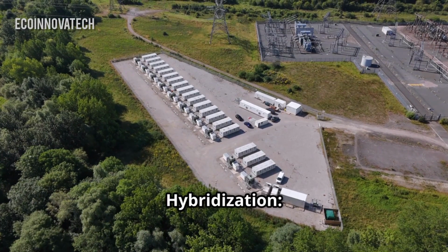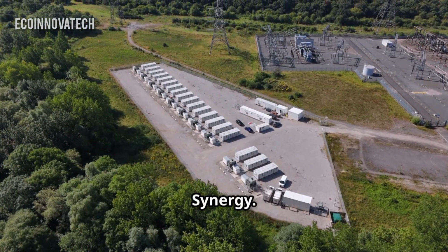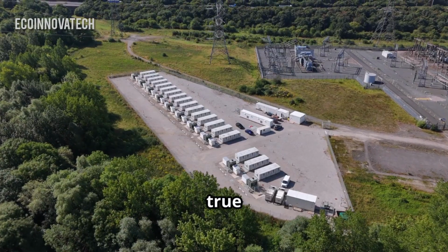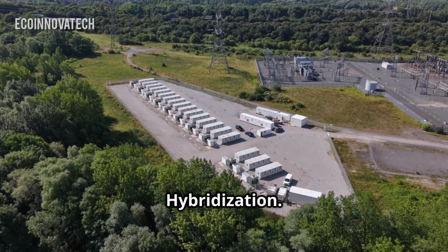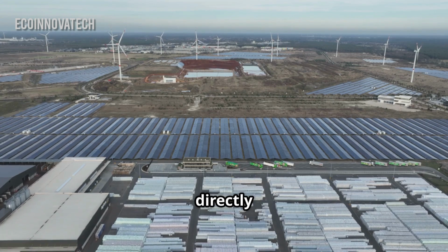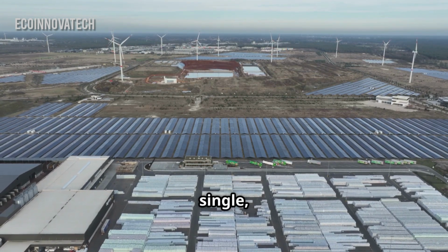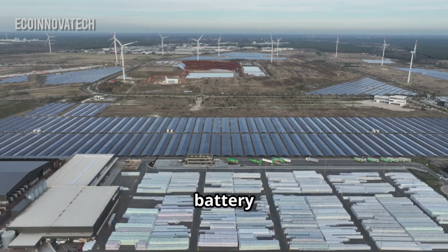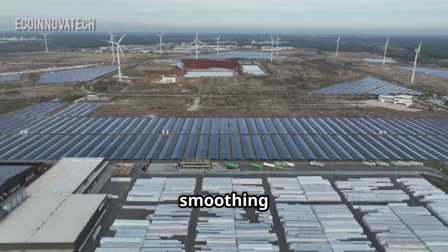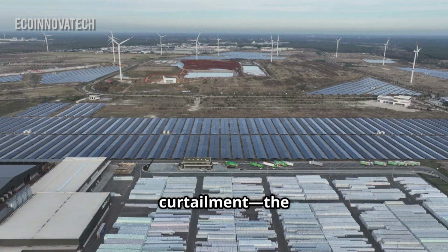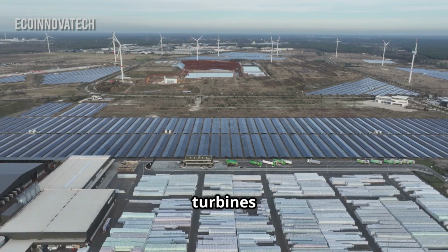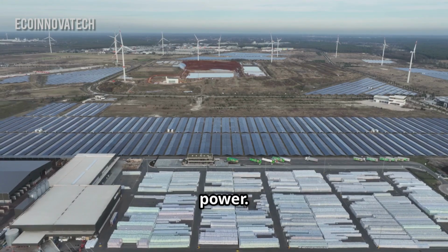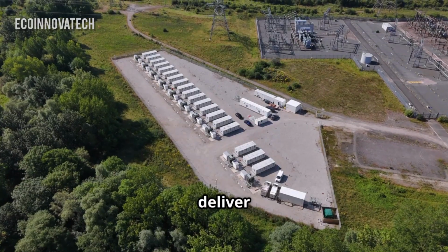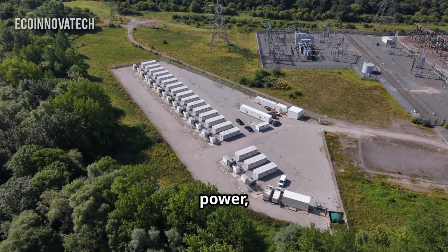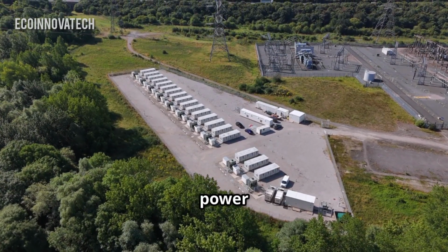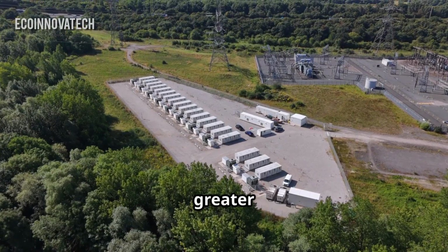Renewable hybridization: the ultimate synergy. When these technologies are brought together, the true transformation occurs. By co-locating a BESS directly with a solar or wind farm, we create a single, dispatchable asset. The battery absorbs energy during peak production, smoothing out the variable output and preventing curtailment, the wasteful practice of shutting down turbines or panels when the grid can't handle their power. The result is a hybrid power plant that can deliver clean, reliable 24/7 power, behaving on the grid just like a conventional power station, but with zero emissions and far greater flexibility.